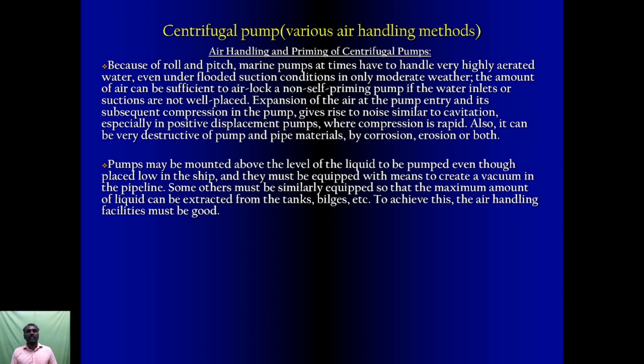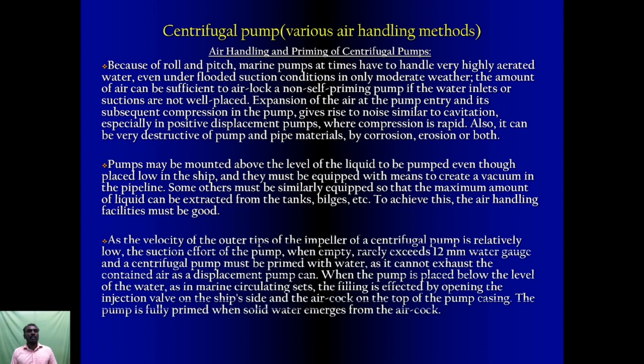Some others must be similarly equipped so that the maximum amount of liquid can be extracted from the tanks, bilges, etc. To achieve this, the air handling facilities must be good, as the velocity of the outer tips of the impeller of a centrifugal pump is relatively low. The suction effect of the pump when empty rarely exceeds 12 mm water gauge, and a centrifugal pump must be primed with water, as it cannot exhaust the contained air as a displacement pump can.